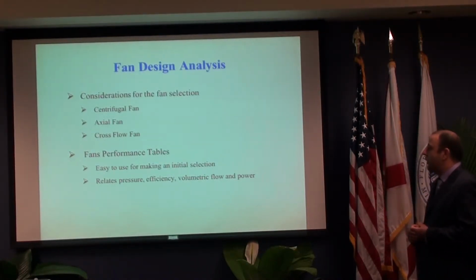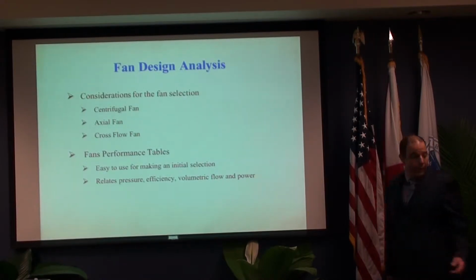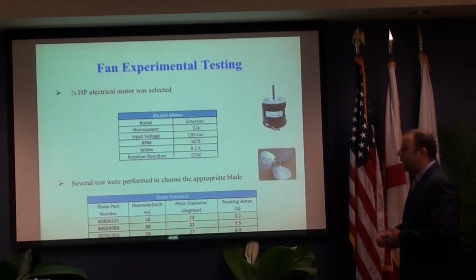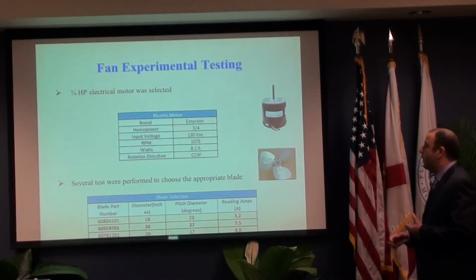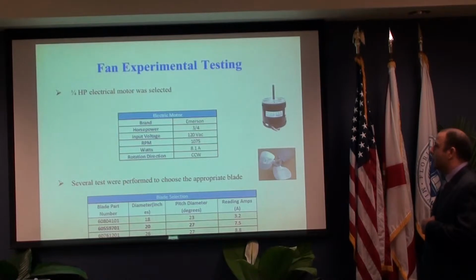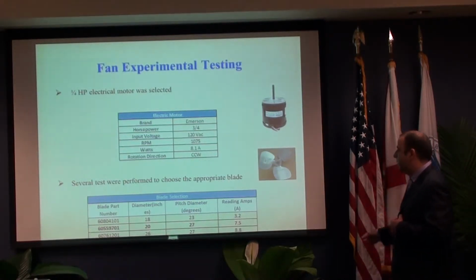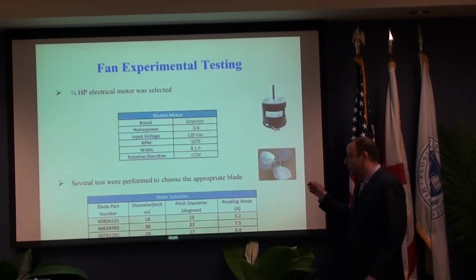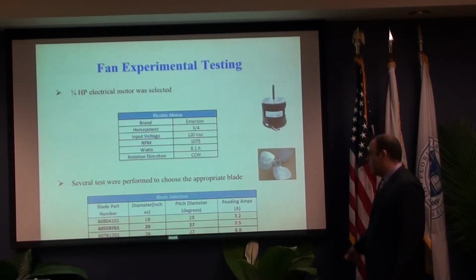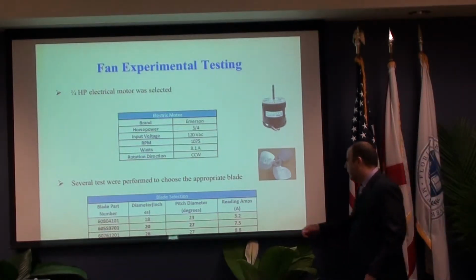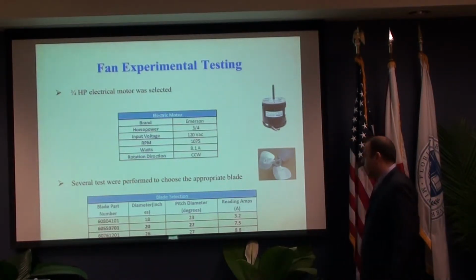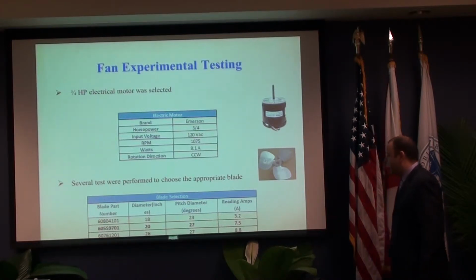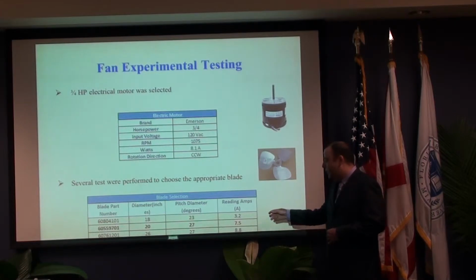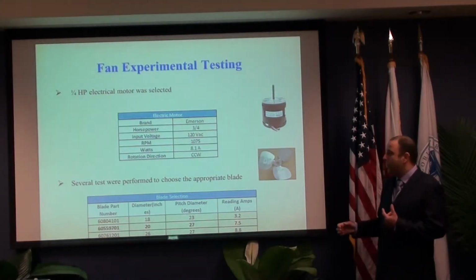The second analysis we did was the fan performance table. Using the fan performance table, it's easy to make an initial selection. It relates pressure, efficiency, volumetric flow, and power. But due to the lack of this table, we had to do 2 experimental tests. We chose a 3/4 electrical motor with 4 speeds. We tested 3 different blades, and we measured the current from the motor specification. From the first column, we have a reading of 3.2, the second one 7.5, and the last one 8.8. We chose the second one because the first one is too low, and the last one is too high for the specification of the motor.